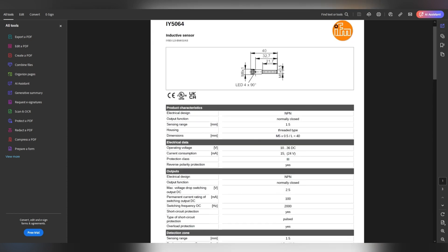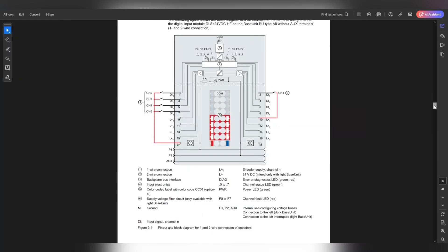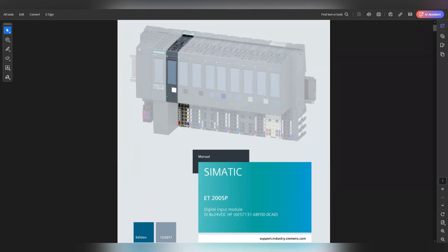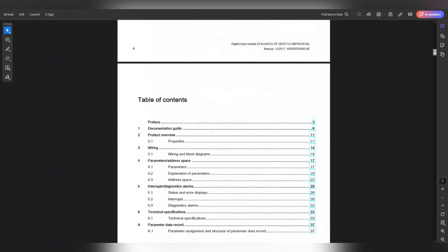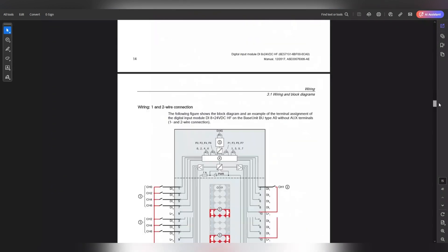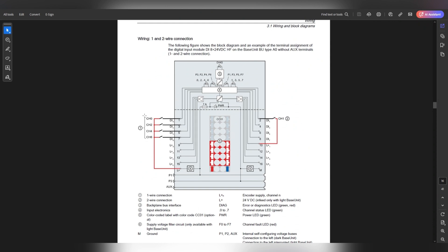I've also selected a Siemens digital input card here — you can see the part number. This card sources the voltage. Looking at page 16 of the datasheet, this is how you connect it with one wire or two wires. You give it 24 volts — you receive 24 volts from this digital input card. When your sensor switches on, it closes that circuit, and then gives 24 volts to the digital input.